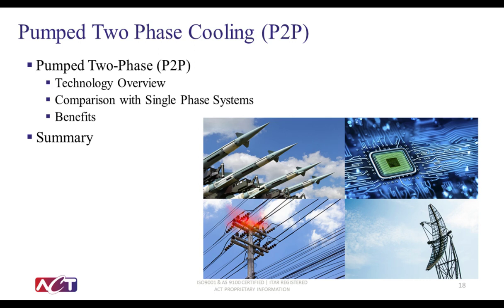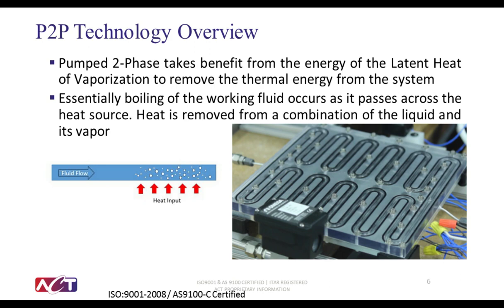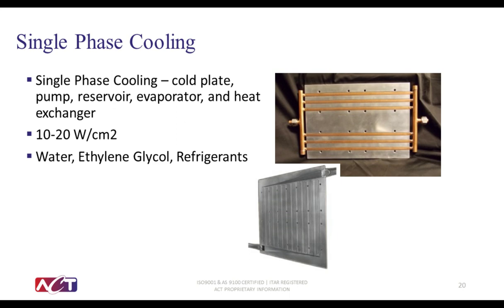Let's start with an explanation of the technology. P2P systems are designed such that the working fluid enters the heat source close to its saturation temperature. When the working fluid comes across the evaporator surface, boiling occurs, and the latent heat absorbed by this phase change is used to remove waste heat from the evaporator. This thermal management solution is much more efficient than traditional pumped liquid systems.